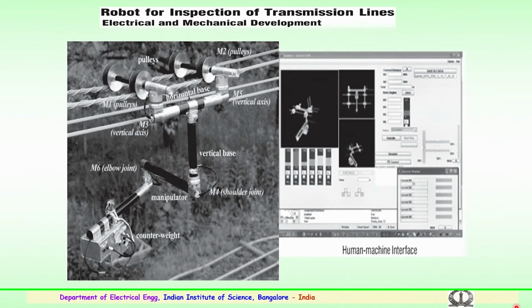Recently, equipment or gadgets like the robot are being used particularly for the inspection of transmission conductors or lines, for both electrical and mechanical related issues. Here this robot basically acts as a human machine interface. From tower to tower, the robot is used and it tries to identify the mechanical deformities of the conductor strands and the distances at which the conductors are placed, and it gives the information to the computer, where it could be very helpful in rectifying the damages which have occurred over a period of time on the conductors. So, a very important development which is being used.